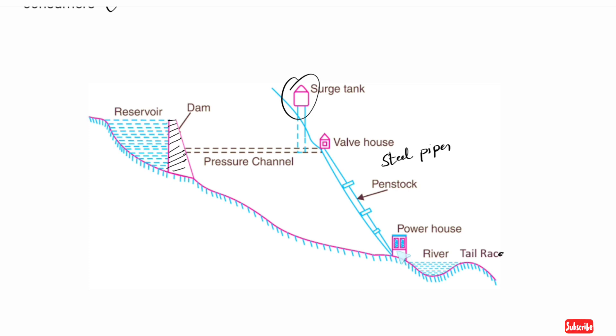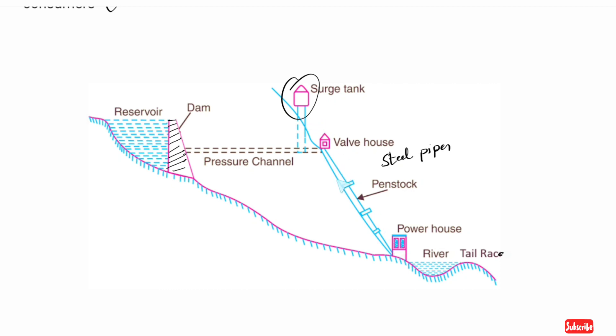Here is the powerhouse. If there is a problem in the powerhouse — for example, the turbine gate closes — the water in the pipe has nowhere to go. The pipe outlet is closed, and water pressure builds up. To handle this, a surge tank is placed along the penstock. When the valve closes, excess water flows into the surge tank, which absorbs the pressure surge and stores the water.